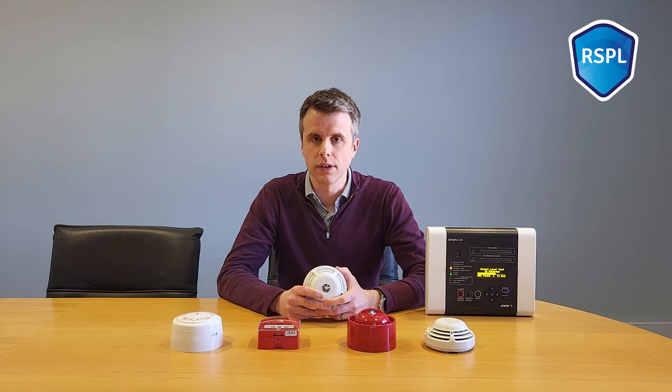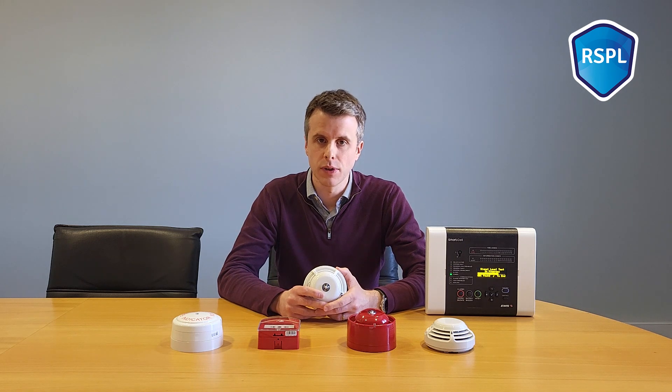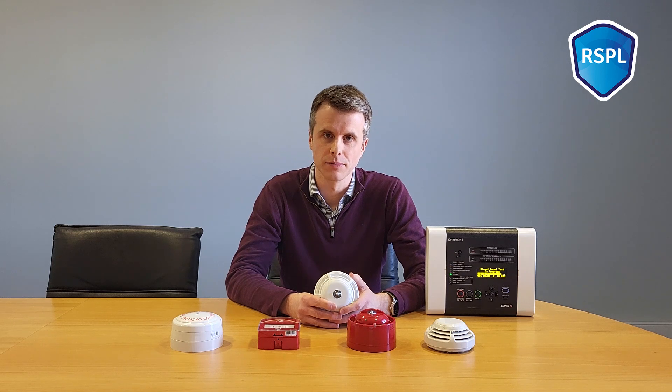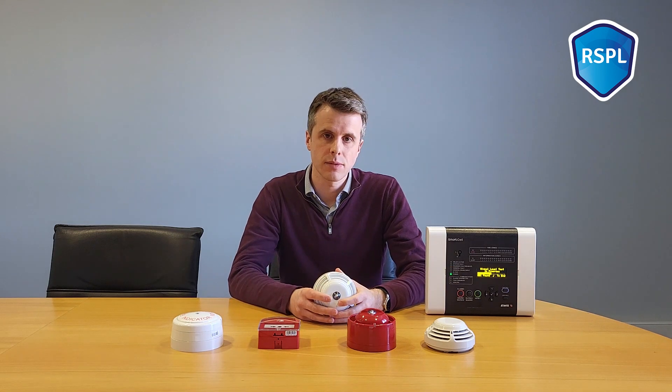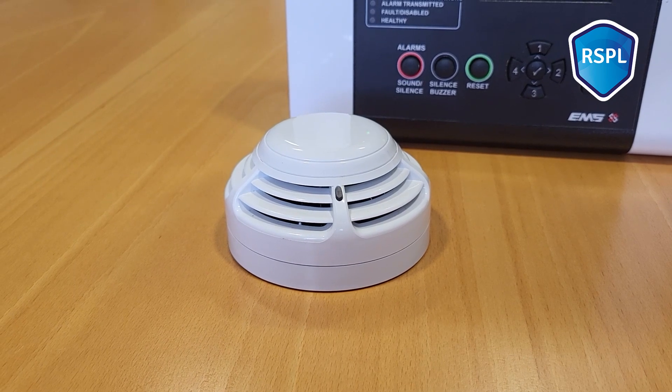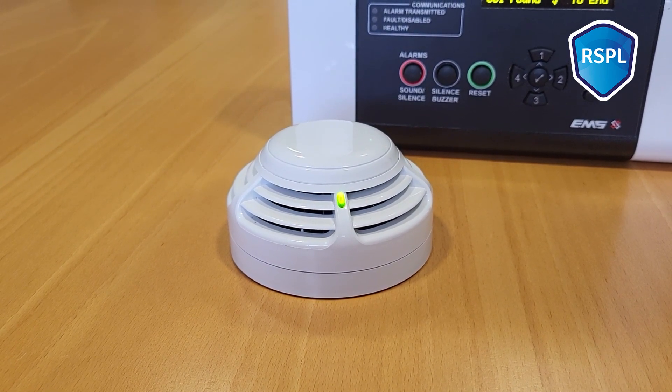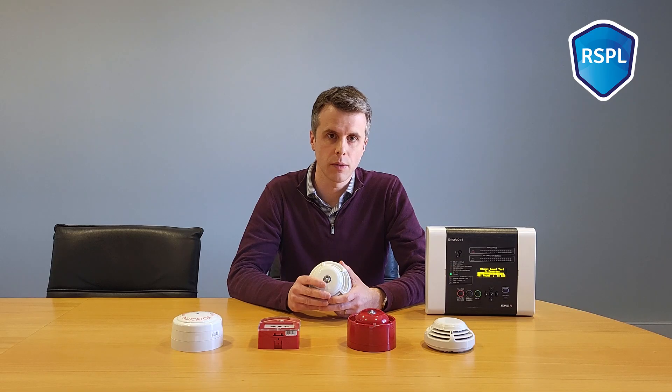We are in the RSPL building in Drumcondra in Dublin right now, and this is a building with thick concrete walls and floors. This building is bigger than what would normally be recommended for a Smart Cell installation. But as you will see, the wireless range in this system is extremely capable. I've put the panel into signal level test mode, and as long as this LED is flashing green, the signal is good. If the LED ever flashes red, it means the signal isn't strong enough. So let's see how we get on.